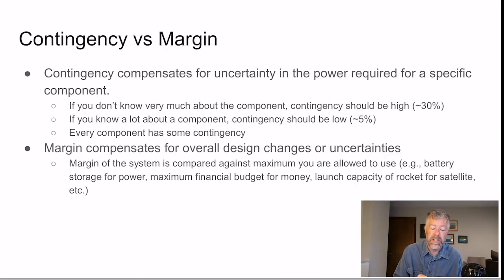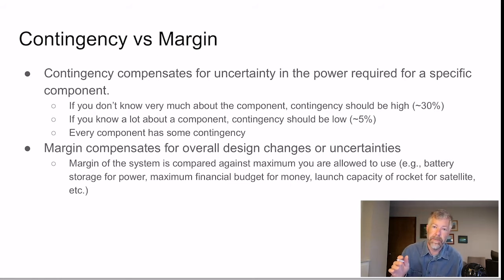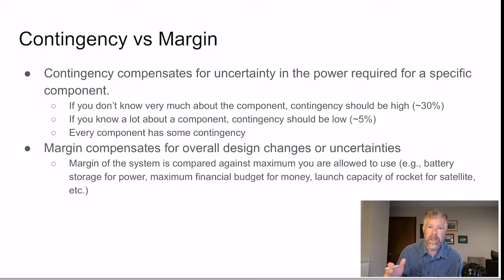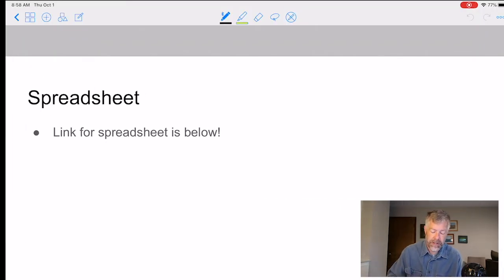There is a key difference between contingency and margin. Contingency is on individual components and reflects uncertainty in power requirements for a specific component — large contingency for uncertain components (say 30%), small contingency for well-known components (say 5%). Margin, on the other hand, compensates for overall design changes at the system level.